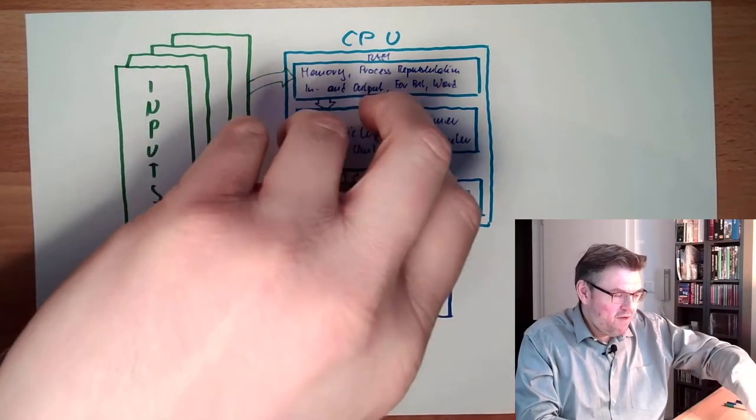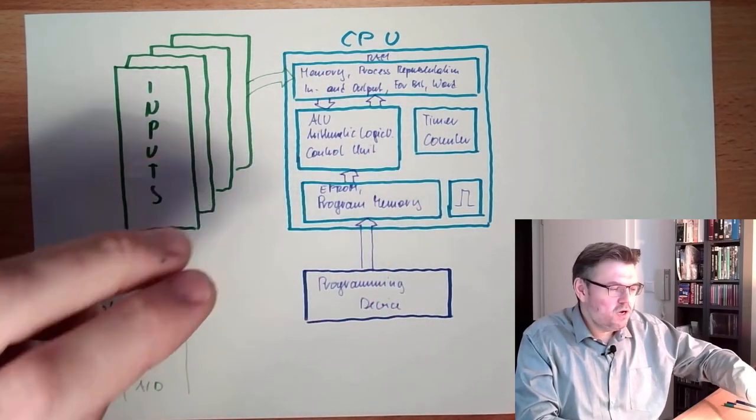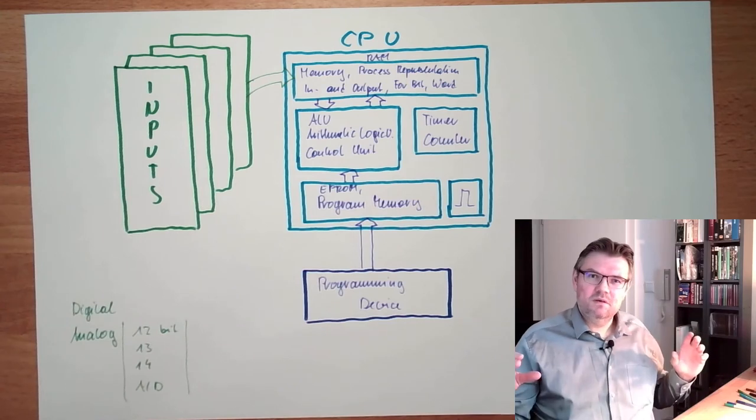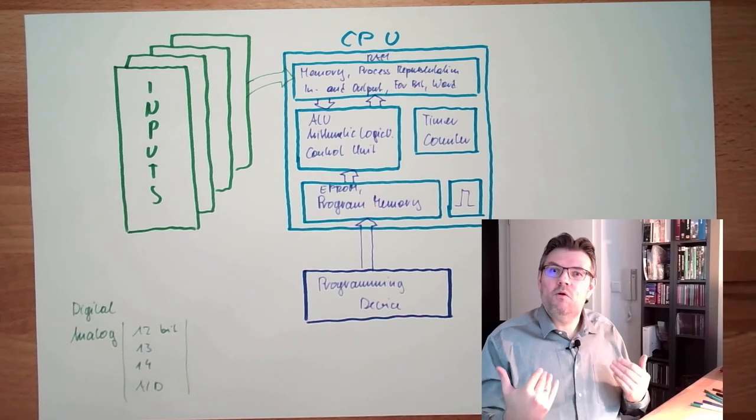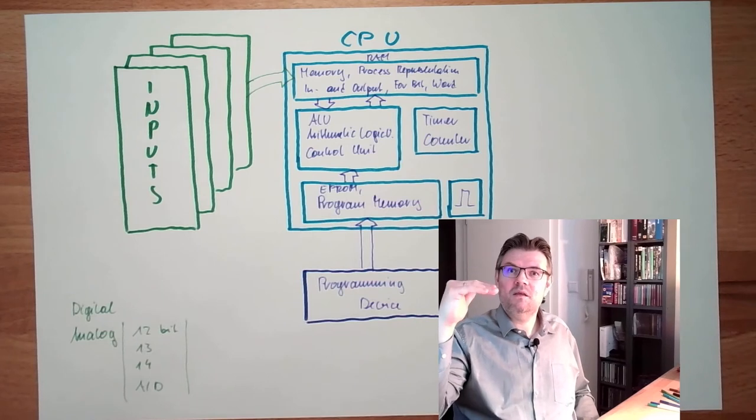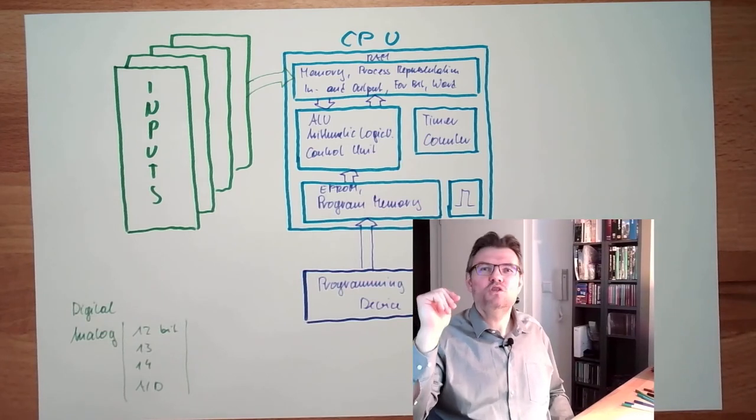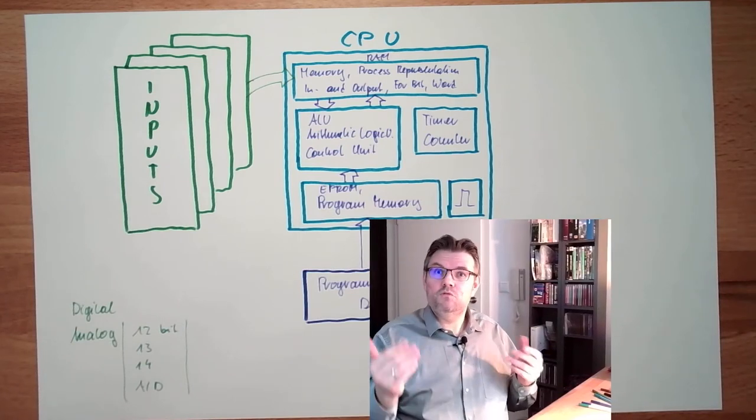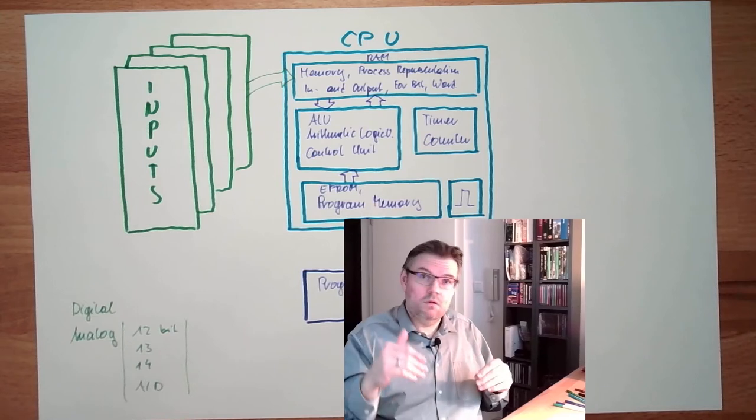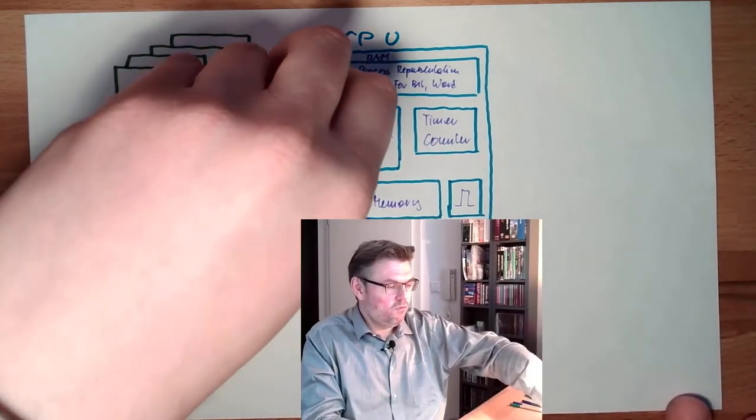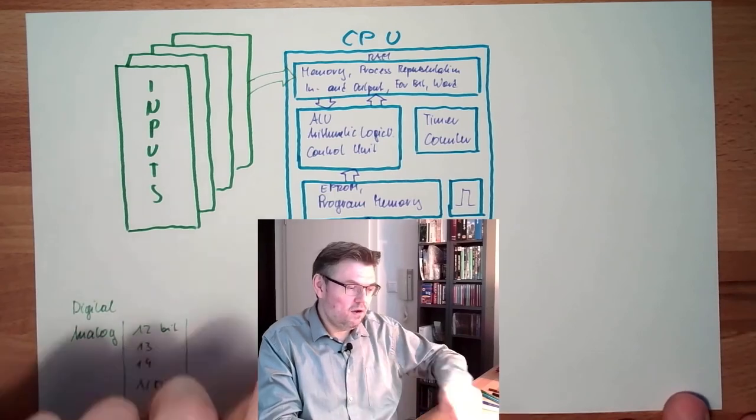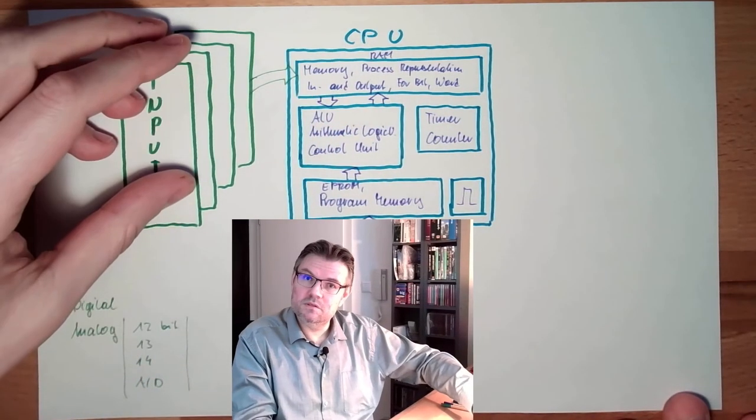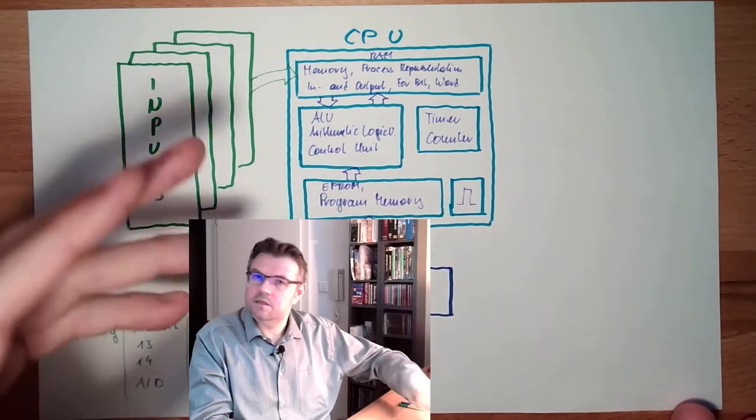Because whenever the program is executed, during program execution, I want to have a consistent state of the inputs. I do not want that an input is changing for my logic during process execution. I have a command, I read out the input, then I have the next command, I read the same input, and suddenly it has a different value. This should not happen. However, the real world does not know where in my program execution I am. So I cannot read directly from the input card. I will read from a so-called process representation, a snapshot of the inputs. And then I will execute the command, and then I will do the next snapshot.